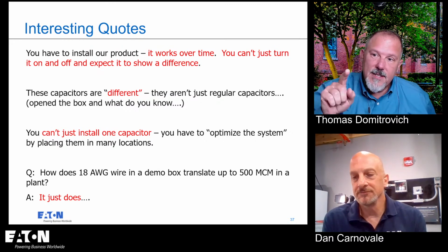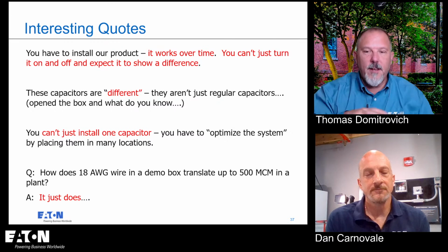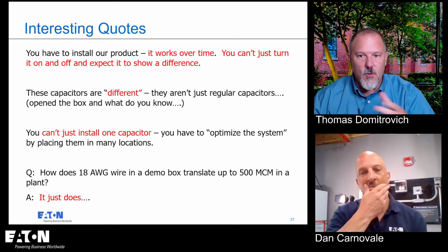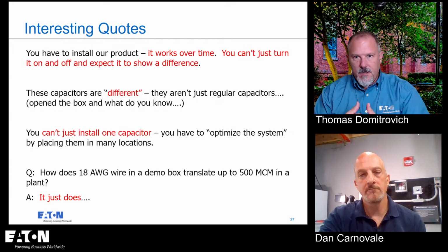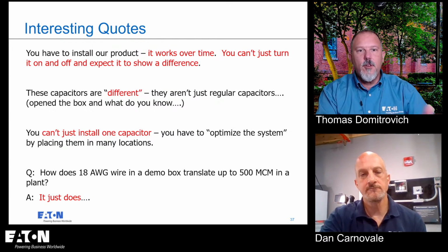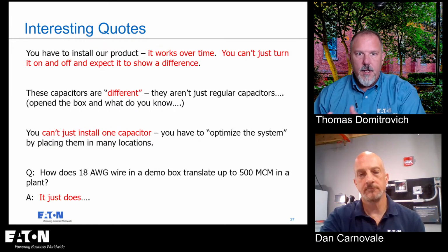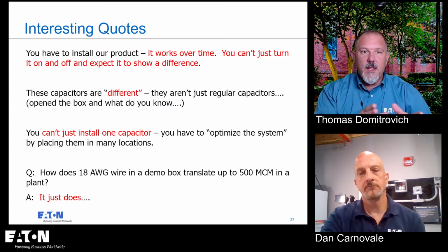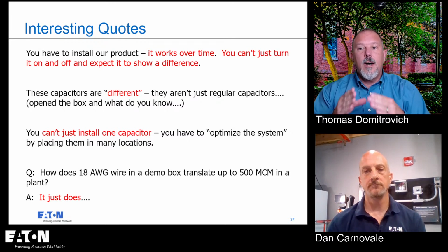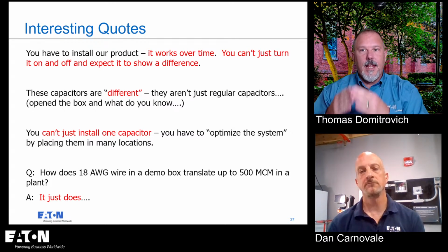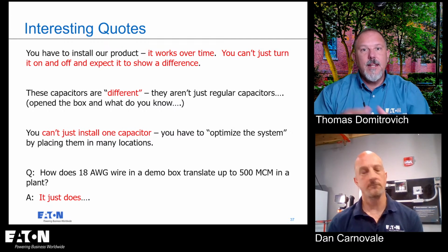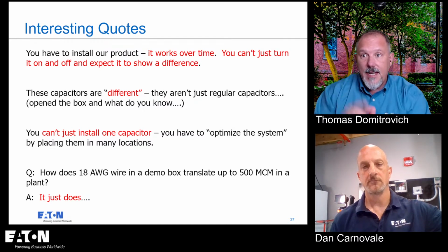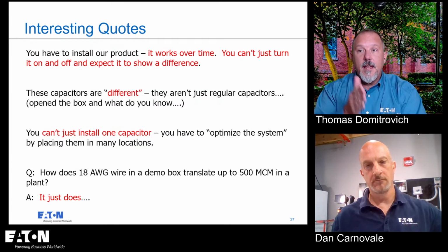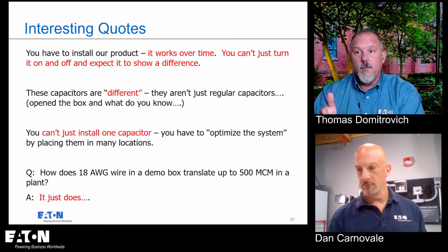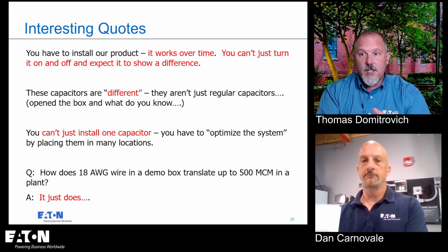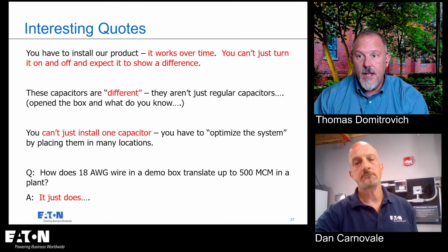Now, Santiago brought a good point. In my little advertisements for this whole session, in my opinion, Dan, there's not only a lesson to be learned to not fall for this, but the fundamental principles we're talking about, this whole concept of power factor correction and amps, we can leverage in other areas in the power distribution system. Santiago asks, can you reduce the ampacity of the conductor and the capacity of the overcurrent protective device, reducing the current with a capacitor, or is it not beneficial enough?